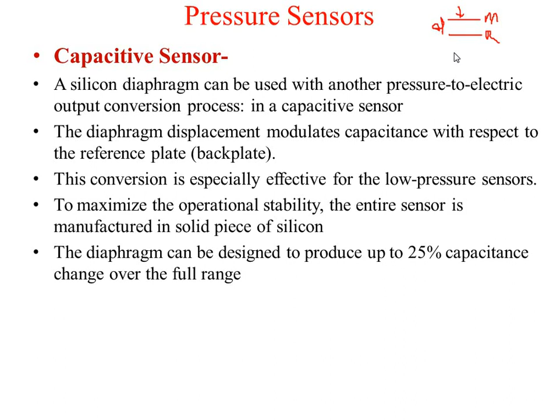To maximize the operational stability, the entire sensor is manufactured in a solid piece of silicon. The diaphragm can be designed to produce up to 25% capacitance change over a full range. That means over a full range of pressure, the capacitance will change from 0 to 25%. The capacitance diaphragm utilizes the displacement of its central position, so that is going to change.